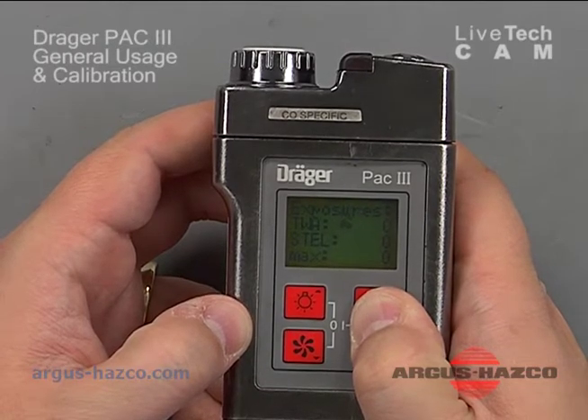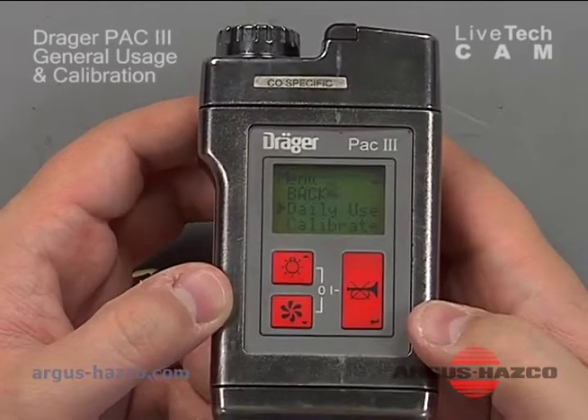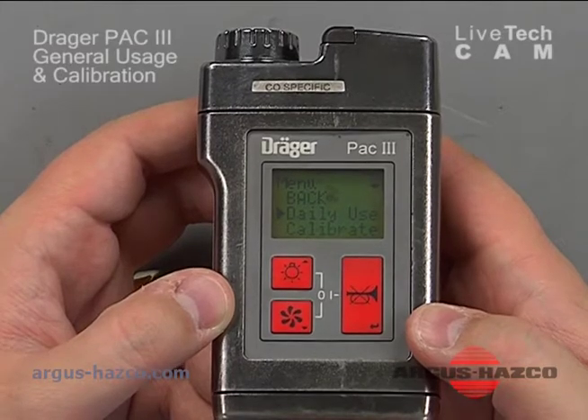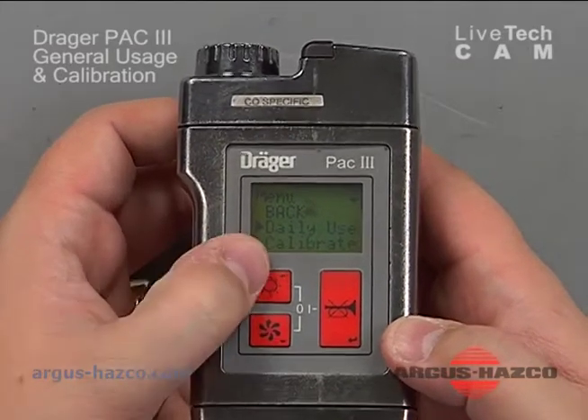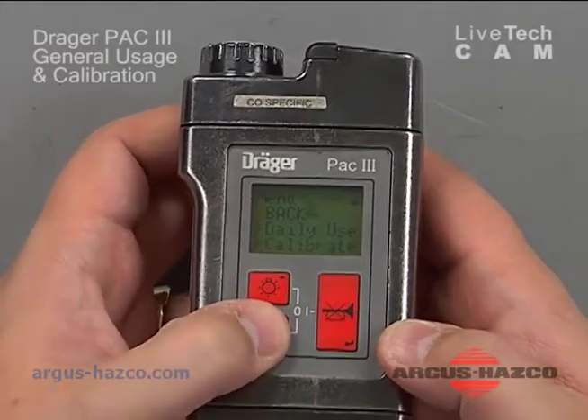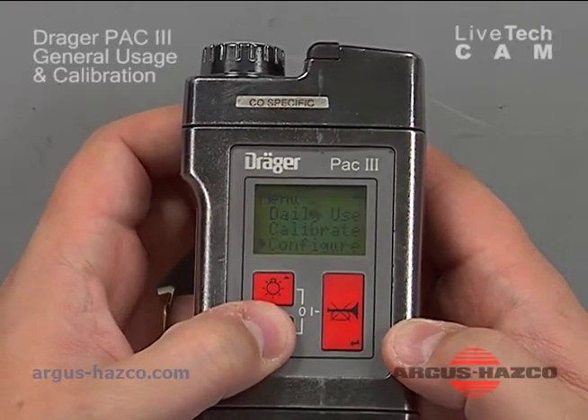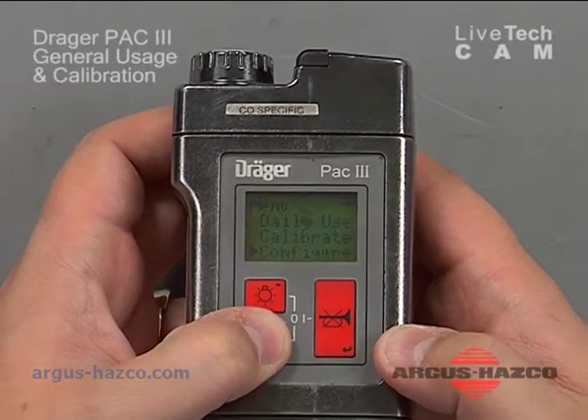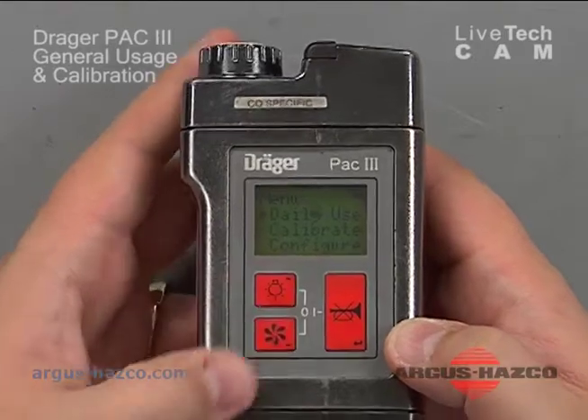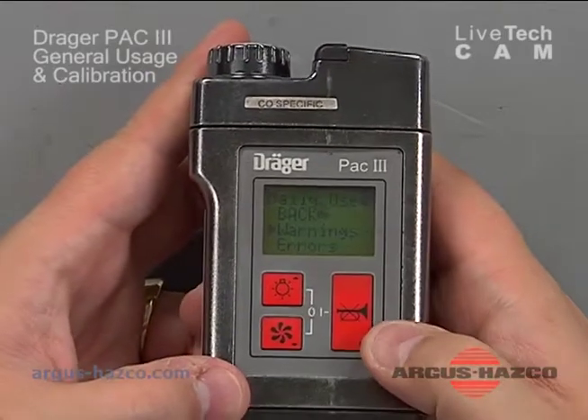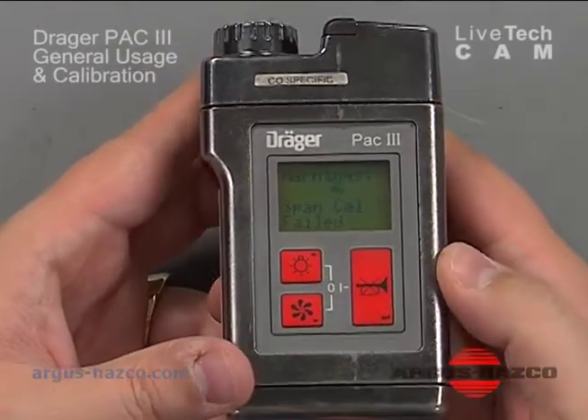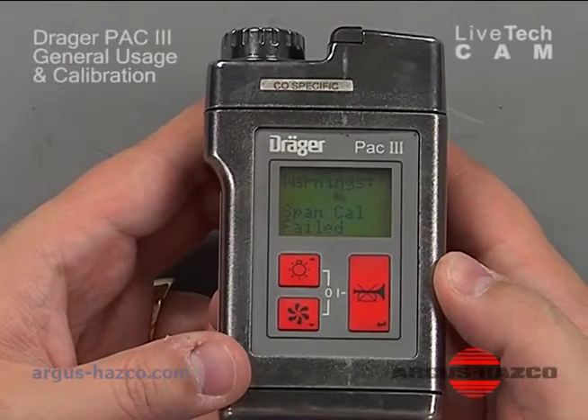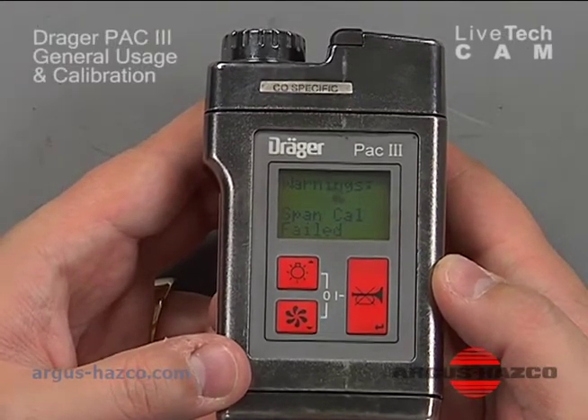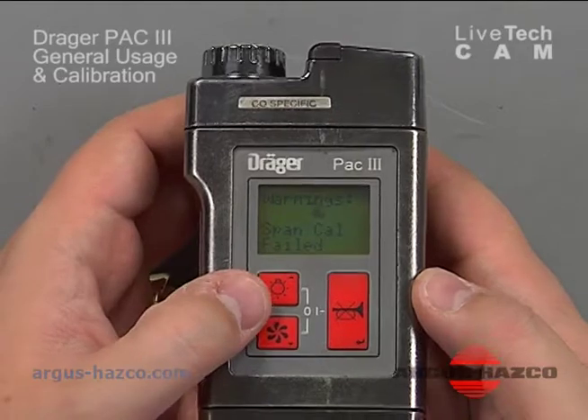and you keep holding it down until it flashes into a menu to give you the back, the daily use, calibrate, and you can scroll down. These are an up arrow, down arrow. So you can scroll down. You can look at daily use, calibrate, configure, and that's it. So if I go into daily use and hit enter, I can view the warnings. It's saying the warning was the span cal failed. So we're going to try to do a calibration on this instrument again.